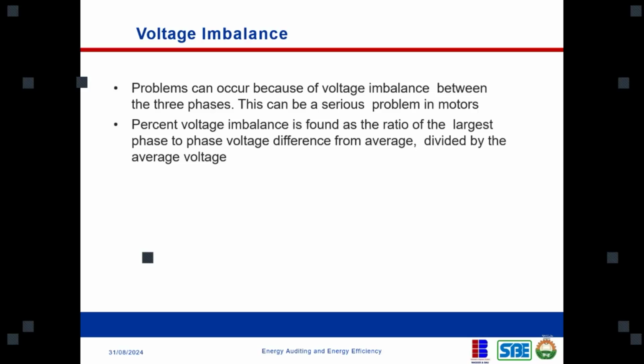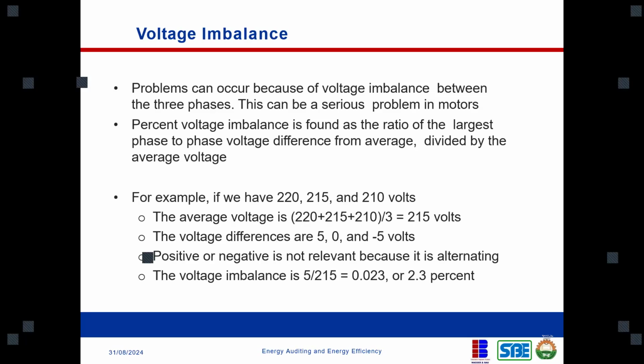Now, this can be a serious problem in motors, especially motors. It can be a very serious problem. Percentage voltage imbalance is found as a ratio of the largest phase-to-phase voltage difference from the average, divided by the average. I'm going to explain, and we're even going to run some examples of how to calculate voltage imbalance.